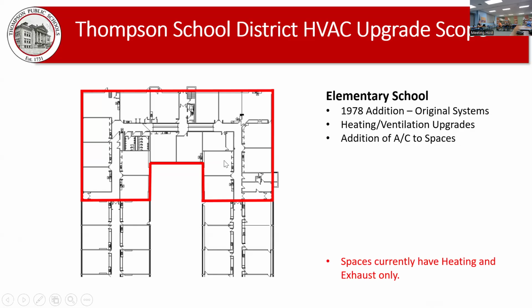The ceiling heights and bar joist construction aren't conducive to running ductwork coming in at one spot with a supply and return main hitting all the branches for the classrooms. So we'd have a significant amount of roof-mounted ductwork here—we just did an entire school this way. The older schools with bar joists and low ceiling heights just don't permit it; we don't get the days of 12-foot floor-to-floor heights with an 18-inch bar joist height. So that would be roof mounted.